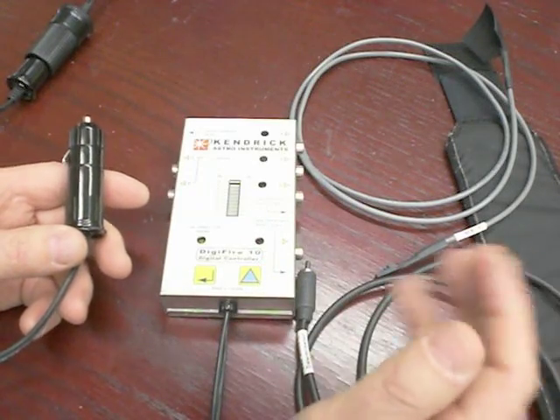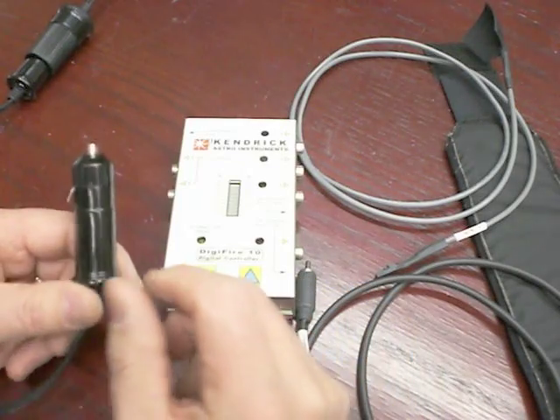Also, if you do have a blown fuse, it means the problem lies not with the controller, but with one of your heaters. So you will need to find out why that is happening.